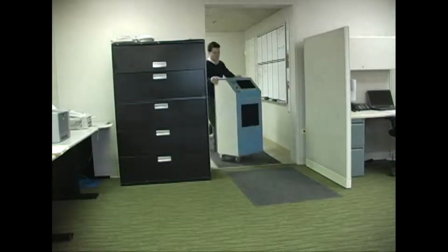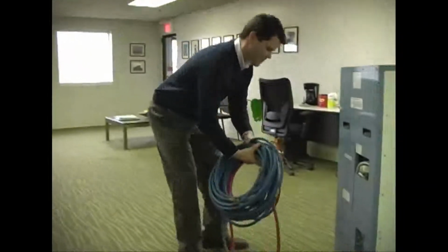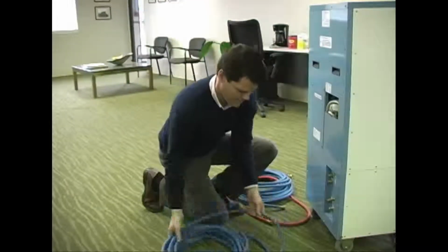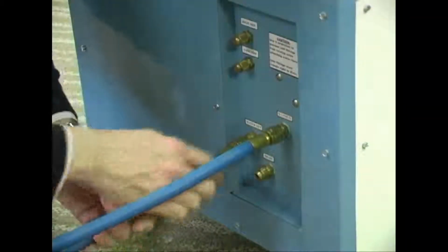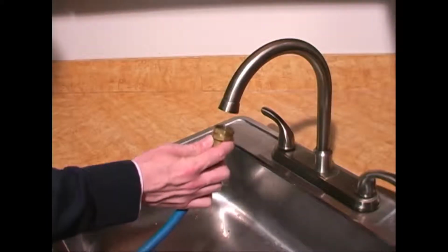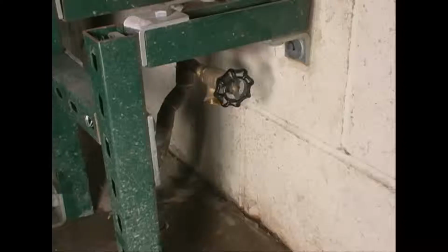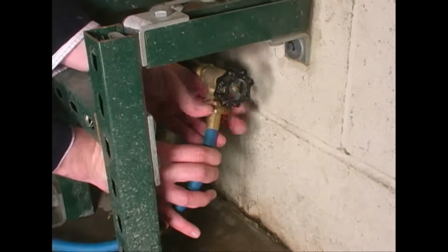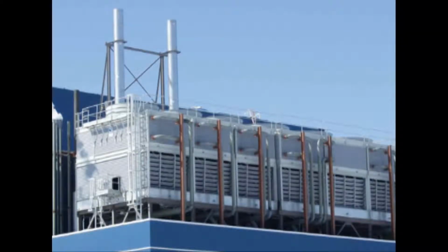An effective way to solve this problem is to use a water-cooled unit in applications where there is no means of venting condenser air. Water-cooled units use water to remove the heat from the condenser. Cold water enters the unit and hot water exits the unit. Using the flexible hose kits provided with the air conditioner, water-cooled units can be easily hooked up to any standard sink, a slop sink in a janitor's closet, a hose bib, or we can even tap into a building's condenser water loop or chilled water supply.